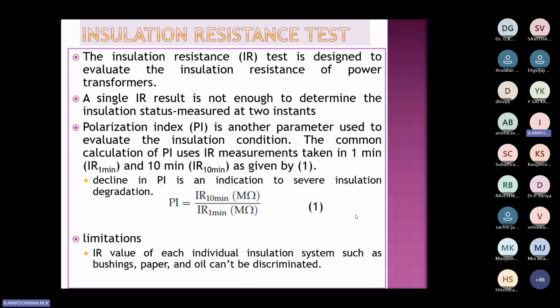But the problem is insulation resistance also varies depending upon the charging or discharging current. So this is another new term I'm introducing. In standards, they will actually apply a voltage for 10 minutes, hoping that after 10 minutes there is no charging current flow. That means your insulation resistance value has to stabilize, so the transient flow is overcome.